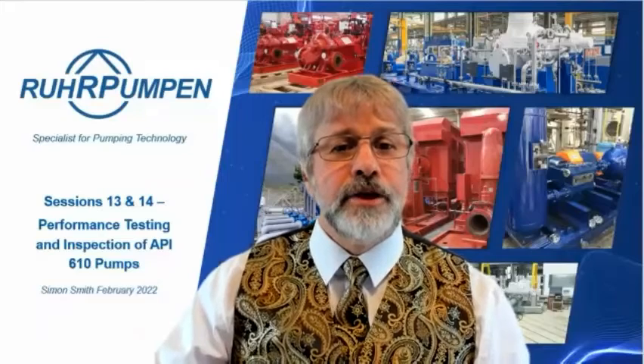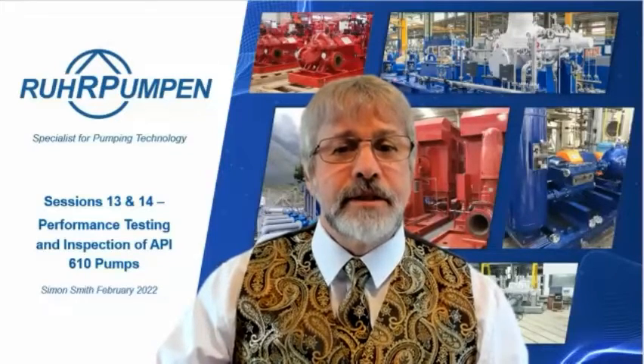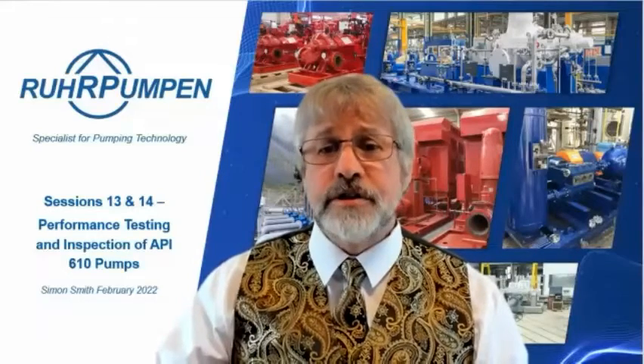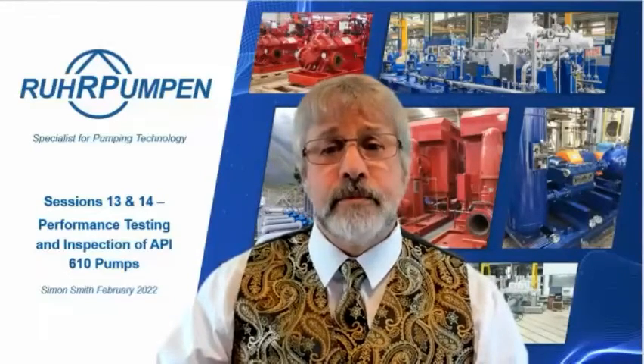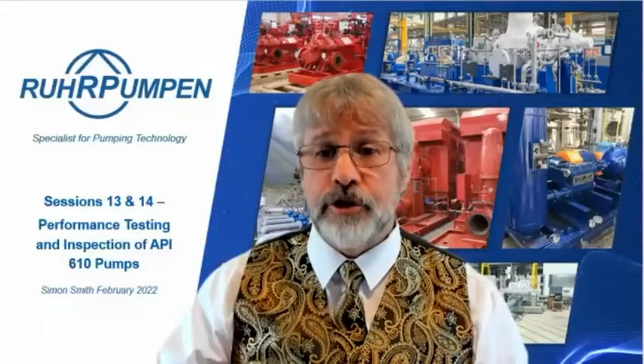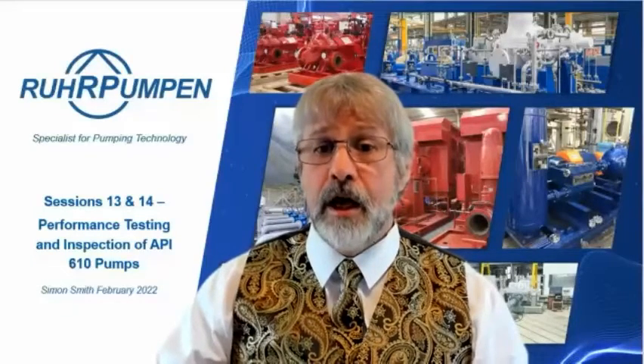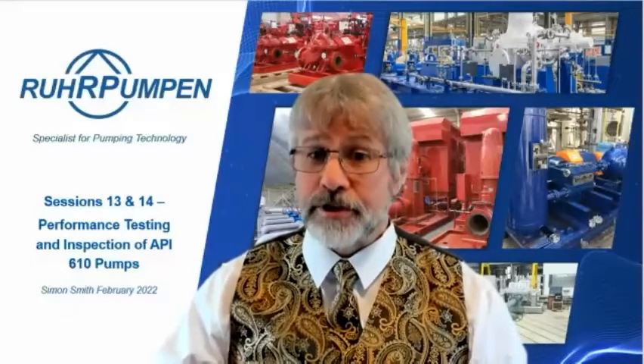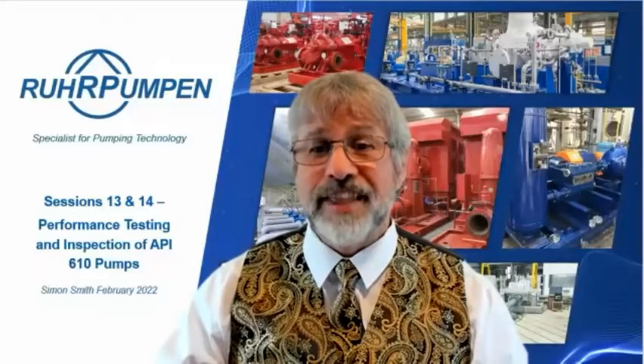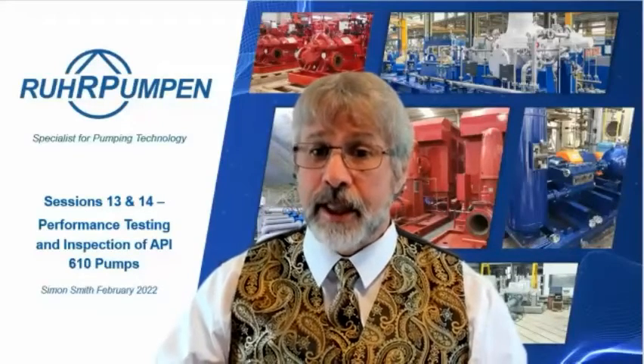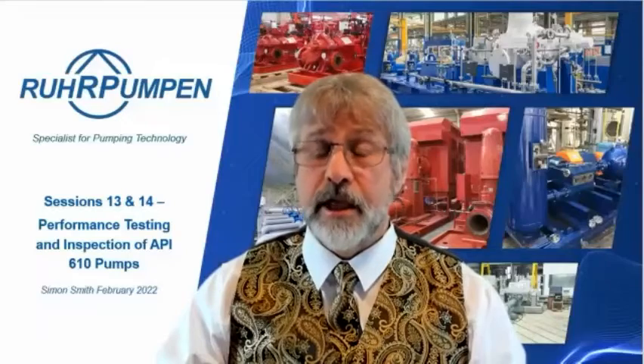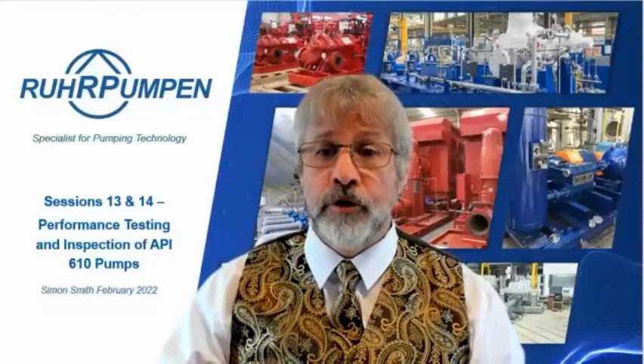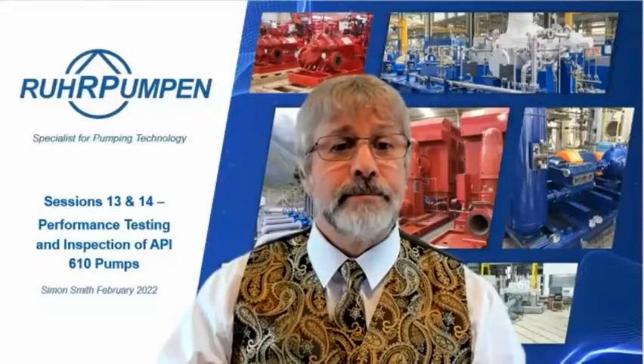Shyam Kumar, is checking of running clearances a must, even if strip test is not applicable? Well, no, because we would be doing those checks before we assembled, or during a final assembly. The measurements of the wearings, for example, the OD of one and the ID of the other, and hence establishing that the clearances are correct. That's a requirement during final assembly.